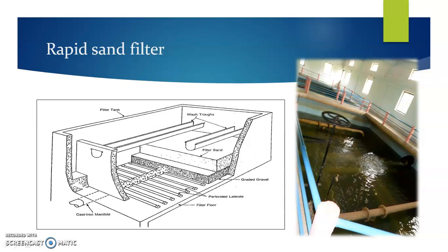Manifold is a large pipe which conveys this filtered water for the next purpose, that is disinfection. This particular filter is very popular in most of the developing countries. These rapid sand filters have been modified to a considerable extent too. They have been modified as multimedia filters, where the rate of filtration is quite high as compared to the conventional rapid sand filters which are used in developing countries like India. These rapid sand filters need to be cleaned almost every day.